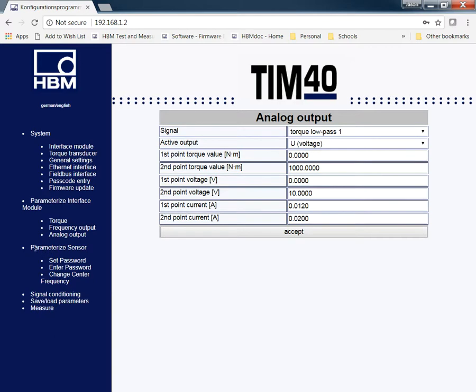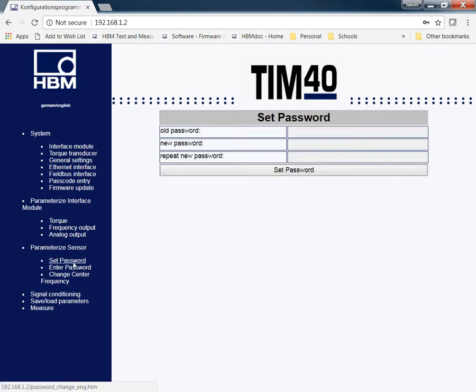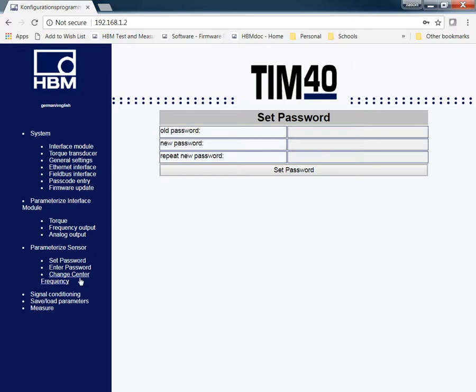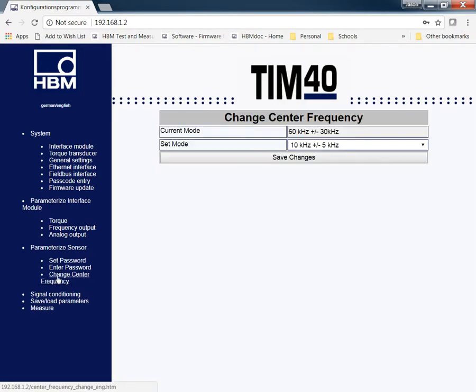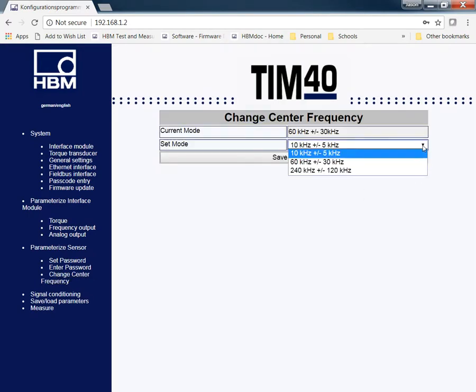Under the parameterize sensor tab, there's an initial password. You can put in your old password and put in a new password if you so desire to do that. Your center frequency, like I mentioned, you can go through and change the center frequency of your actual transducer. There's different options that you can change. Just make sure that this option matches the option that we have in the frequency output that we discussed earlier.